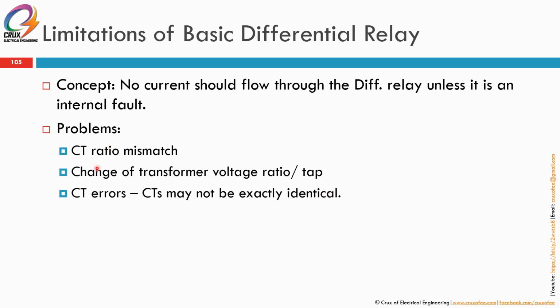For items 1 and 2, we will discuss on the next few slides. What is important is that no current should flow through the differential relay for normal current flow or an external fault, unless the fault is an internal fault. Only during an internal fault do we want the differential relay to operate. At other times we want it to stay stable.